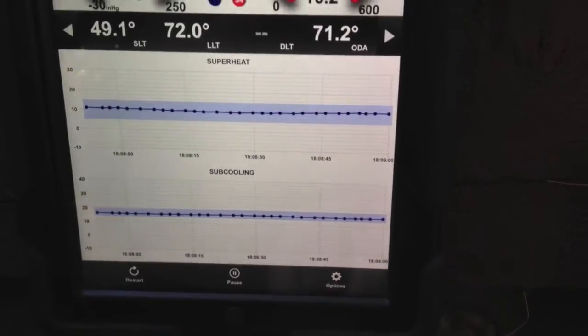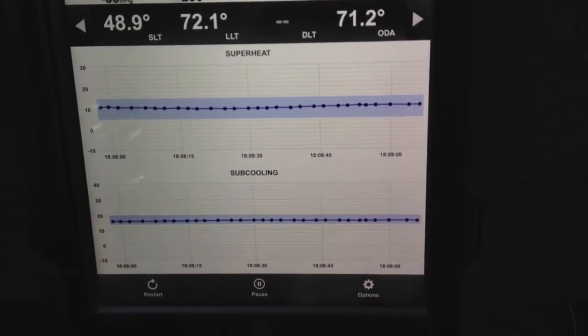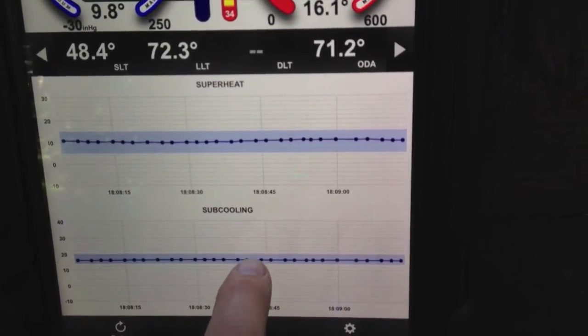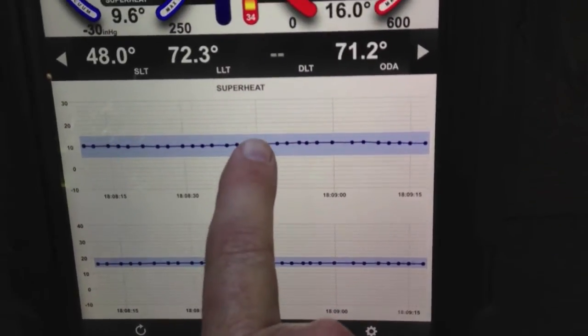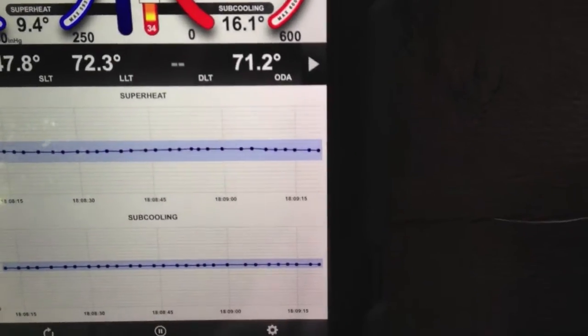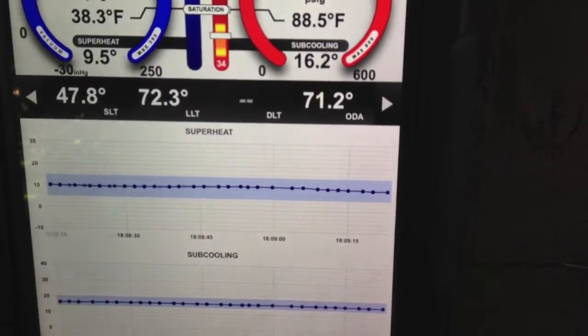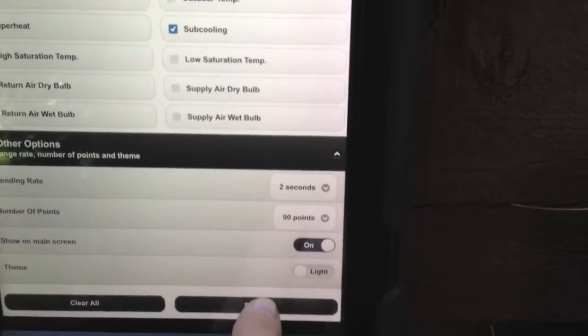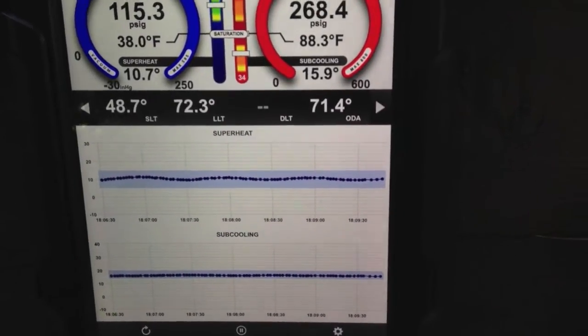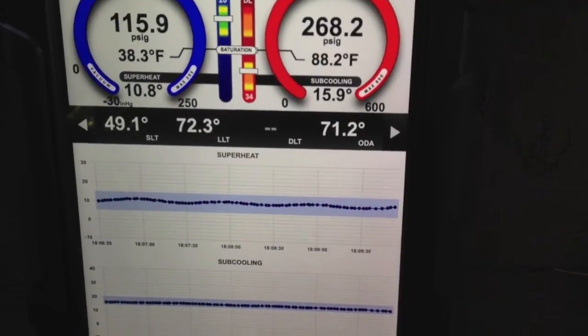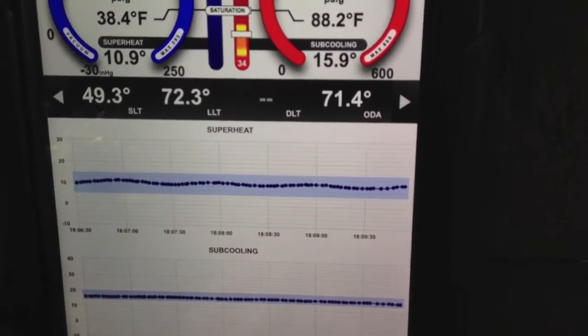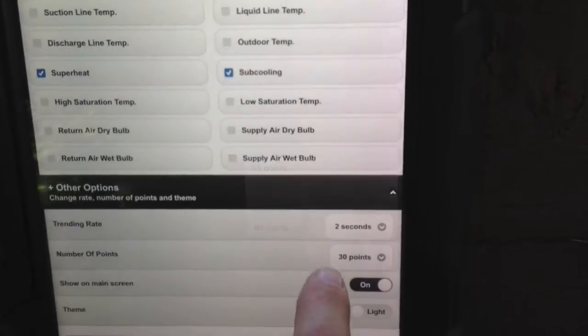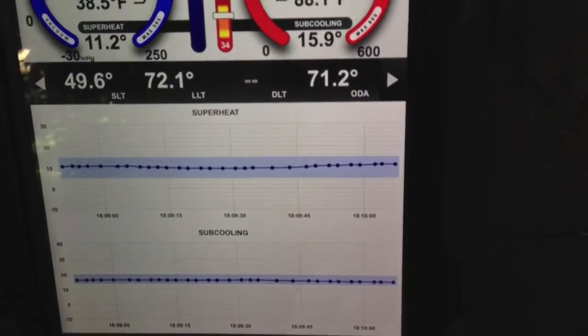You can see superheat and subcooling are dead on in the center of my targets — exactly where they should be. I'm at 10.1 and 16.2. On subcooling, the allowable is plus or minus three, which is why it's a narrower band than superheat, which is plus or minus five. This is 30 points of data at every two seconds. I can go in and change to 90 points and hit submit — it puts up the last 90 points it recorded, held in memory. It just depends on what we want to show; 30 points will do the trick here.